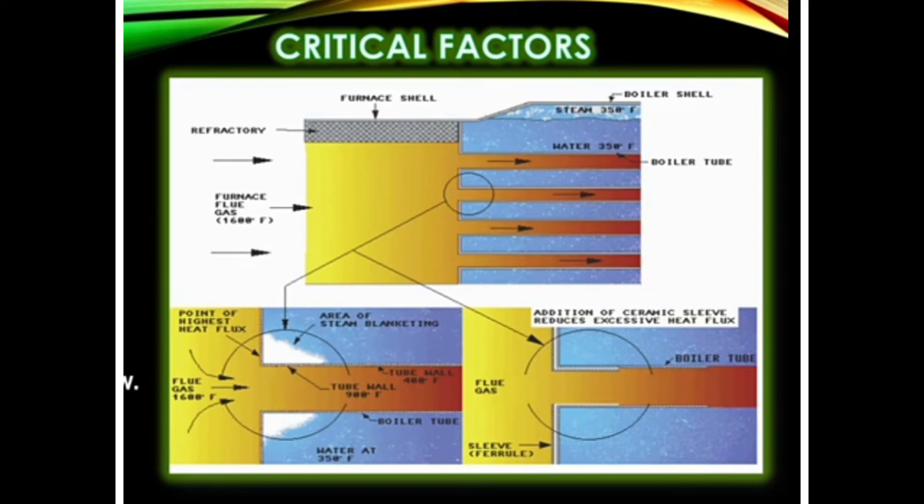One additional point: steam blanketing can also occur due to flame impingement. If your flame is directly touching the tubes, it is called flame impingement. Due to flame impingement, there are high chances of steam blanketing, which will cause overheating of the tube and ultimately lead to its failure.